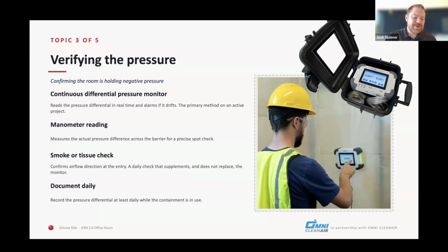At the end of the day, while I jest and joke, buy our machine, we firmly believe it's the best. You want to calibrate it, and I think that's a very operative word that is under-invested in. The market is flooded with thousands and thousands of various versions of digital differential pressure monitors. But the biggest miss we see over and over again is annual calibration. People are using 5-year-old machines that have not been calibrated in 5 years, and when they come in to get calibrated, they're drastically off the first time they've ever been calibrated. So really you've been taking records and making assumptions off of a machine that's just false.